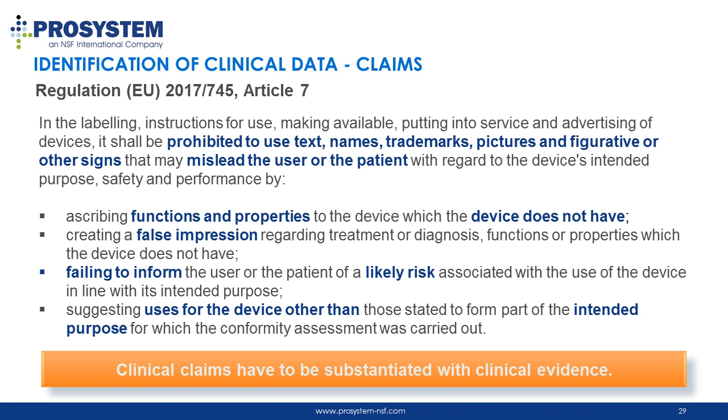So be sure to screen the marketing claims of your device, including web pages and marketing brochures, for clinical claims that need to be covered by clinical data. Clinical claims should also be included in your literature search protocol. Remember that all clinical claims have to be substantiated with clinical evidence.